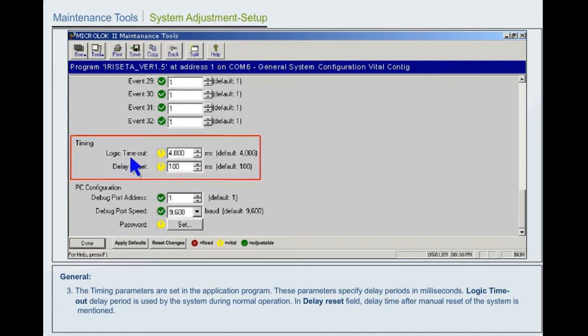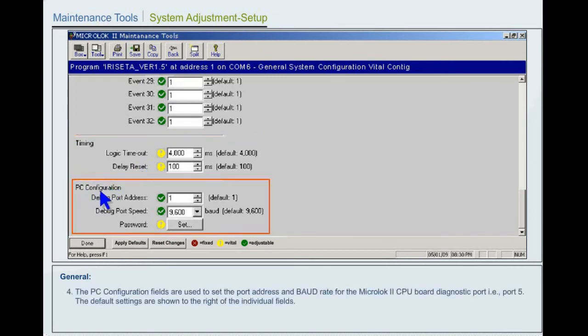Logic timeout delay period is used by the system during normal operation. In the delay reset field, the delay time after manual reset of the system is mentioned. The PC configuration fields are used to set the port address and baud rate for the Microlok II Central Processing Unit Board diagnostic port, that is port 5. The default settings are shown to the right of the individual fields.